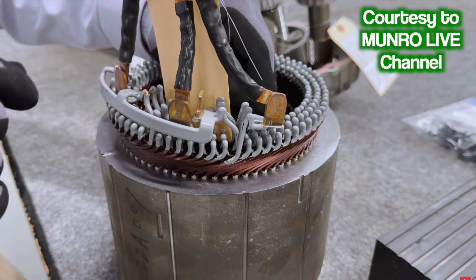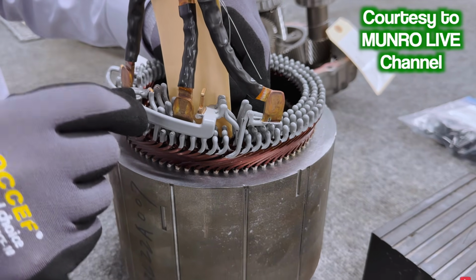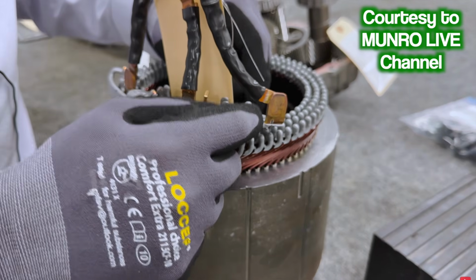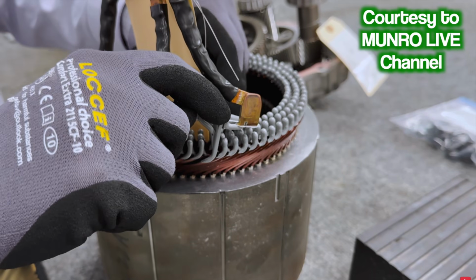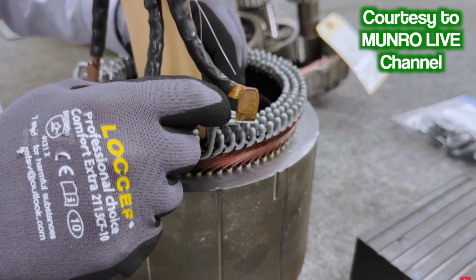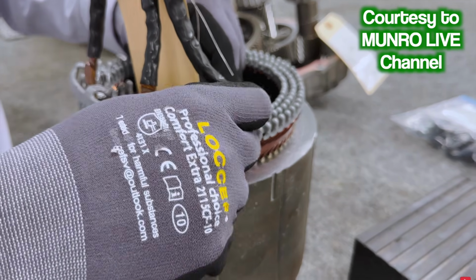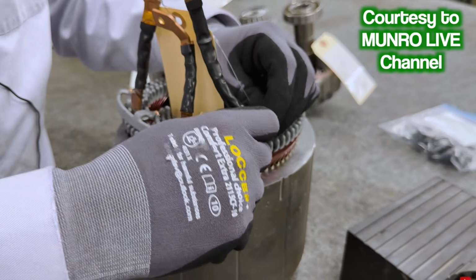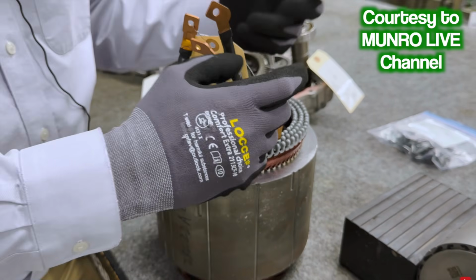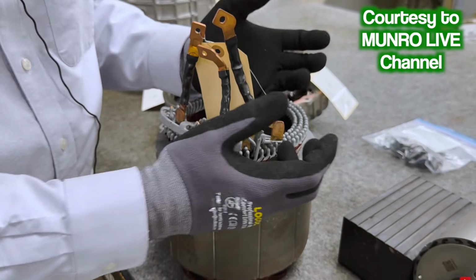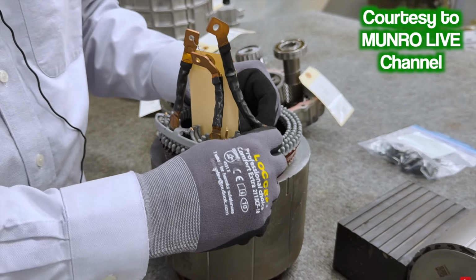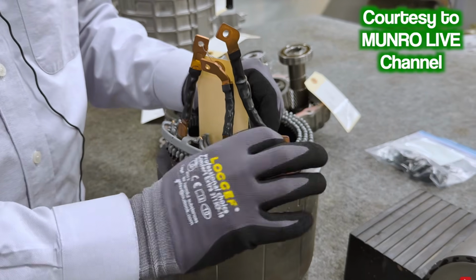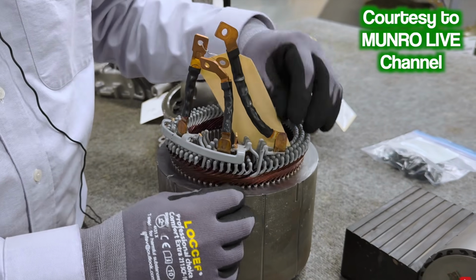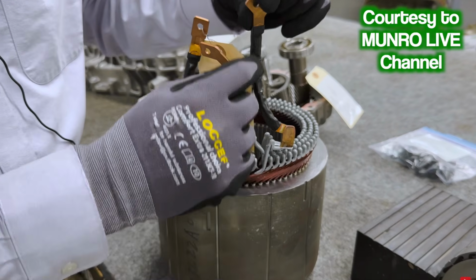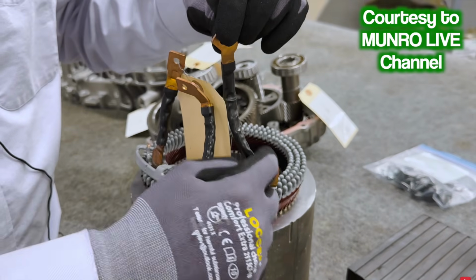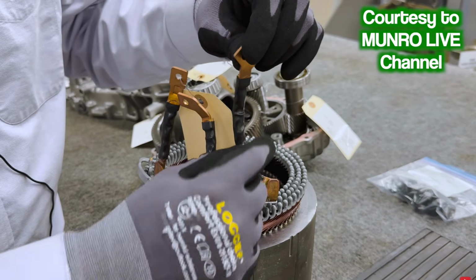The cardinal rule, the general engineering rule of thumb, is that you do not want your electrical connection to also be the thing that carries the mechanical support. You want the mechanical support carried by a mechanical part, and the electrical connection free from mechanical stress. So what happens here is when we run hundreds of amps through this, it heats up.